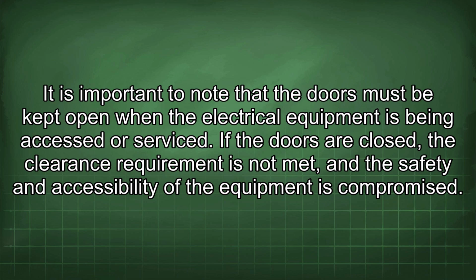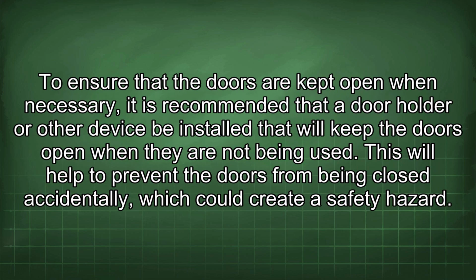It is important to note that the doors must be kept open when the electrical equipment is being accessed or serviced. If the doors are closed, the clearance requirement is not met, and the safety and accessibility of the equipment is compromised. To ensure that the doors are kept open when necessary, it is recommended that a door holder or other device be installed that will keep the doors open when they are not being used. This will help to prevent the doors from being closed accidentally, which could create a safety hazard.